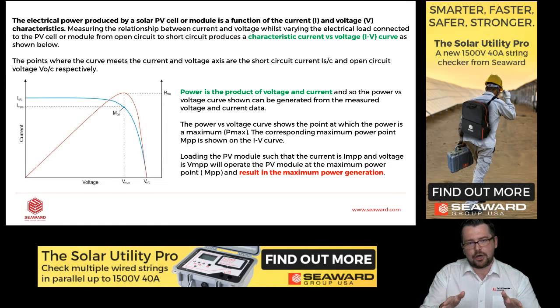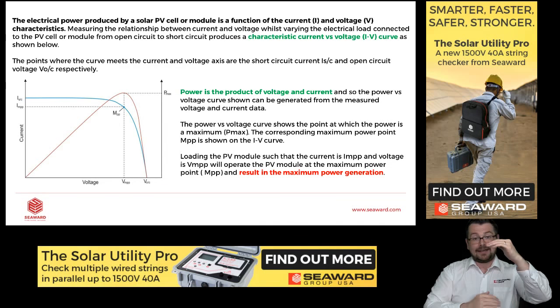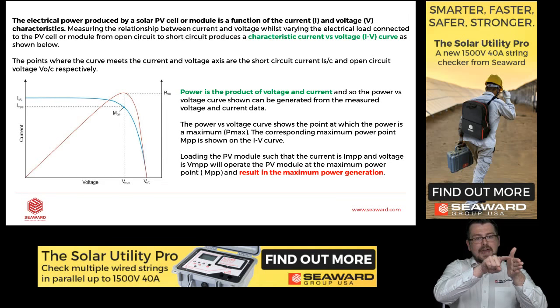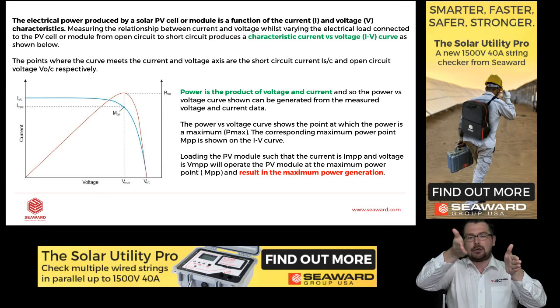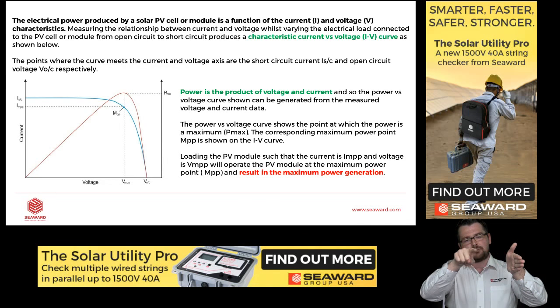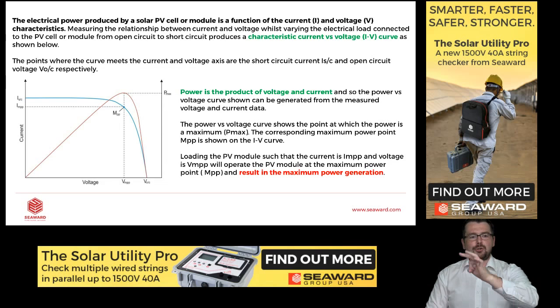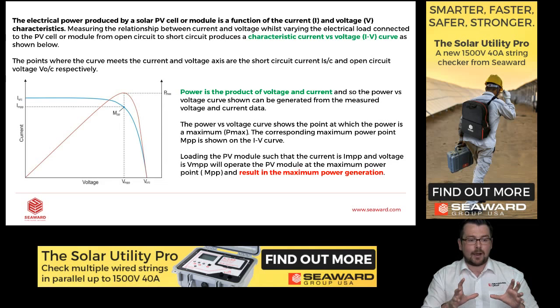So what we do with IV curve tracing is we short out the circuit inside of the instrument, then we vary a resistive load from short circuit current to open circuit voltage. And what we do is we take points along the way. Okay? And what this does is it gives us the characteristic IV curve, but it also gives us the max power point. And the max power point is shown on the IV curve. It's very useful to us. So this is how we generate the IV curve. Now I can tell you a few things we can do with it.